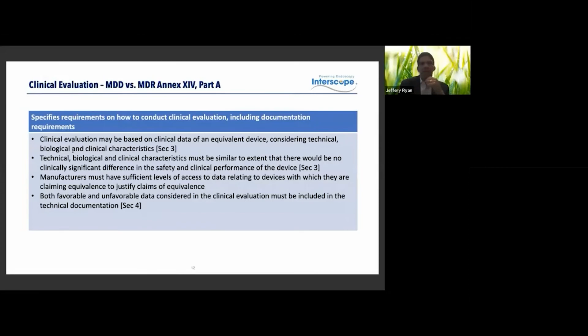If partial equivalence is not acceptable, the FDA used to allow for reference devices as part of a 510K process, and you still can use them with an FDA submission. But you really can't do that anymore. You can't do that here in Europe, and you can only use a predicate of something that's currently available in the market in Europe. Big foot stomp there. So if someone else decided to pursue a path in the United States, you can't double back and say that is your equivalent device that you're trying to map to. Very key distinction to pull away.